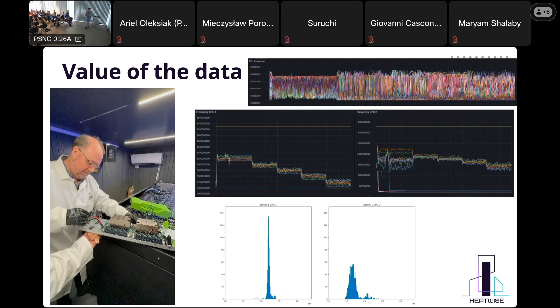The first case: I have a data center consuming 10x, and it has this new cooling system. This cooling system, from the heat rejection unit, can provide 65 degrees, which is totally good for my building's temperature regime and requirements. So what I do, except the losses, I may recapture in a good day 9x of the waste heat byproduct we generated, and an energy reuse factor of 0.9 is achieved.